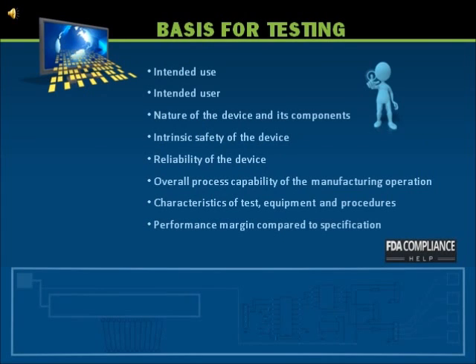In order to be assured a device is fit for the intended use, the firm should decide which characteristics of a device to test or inspect, and to what detail is required for conformance. Decisions on what to test and how to test are made during the product and process development phase and recorded in the device master record.